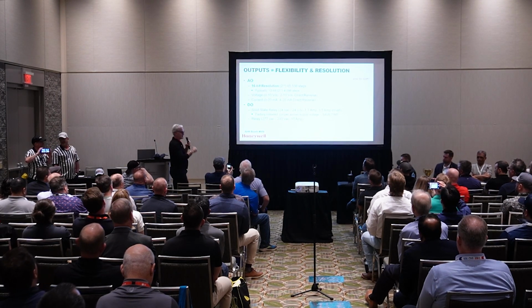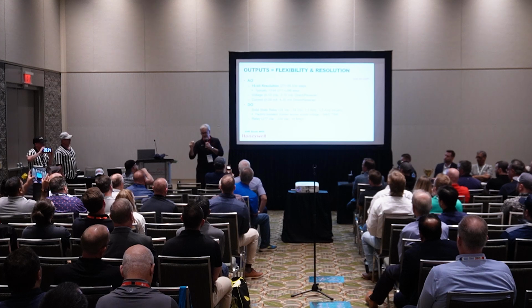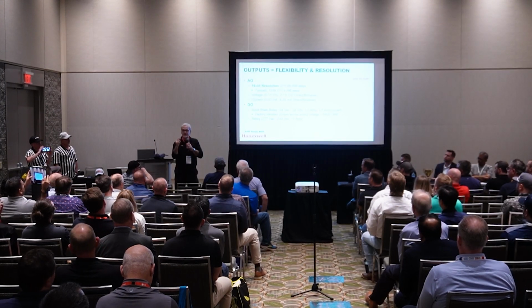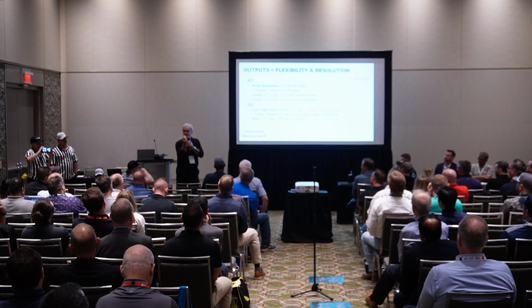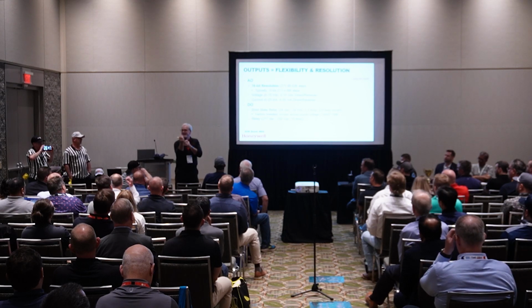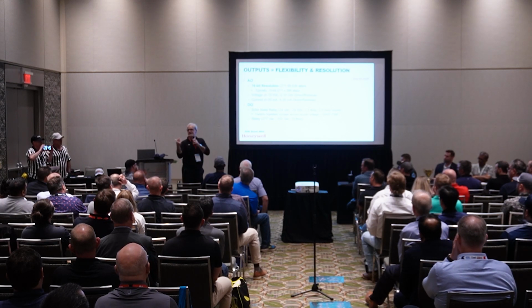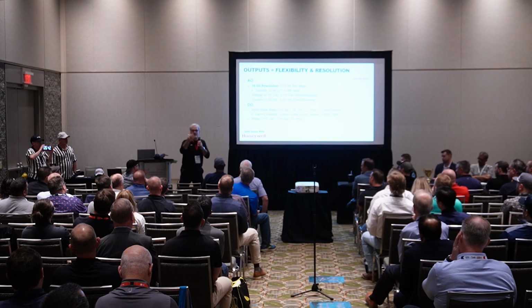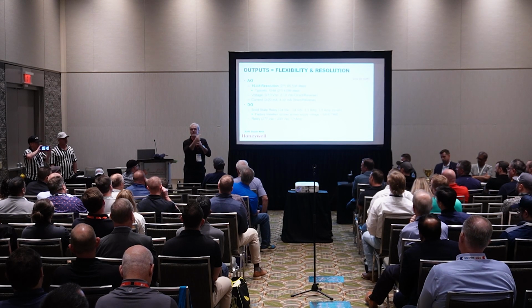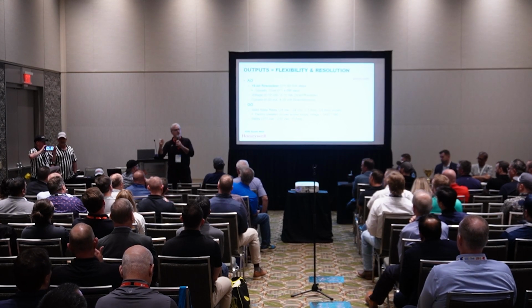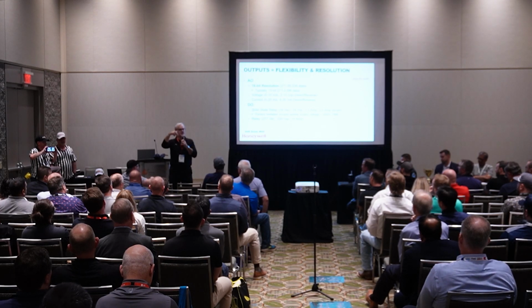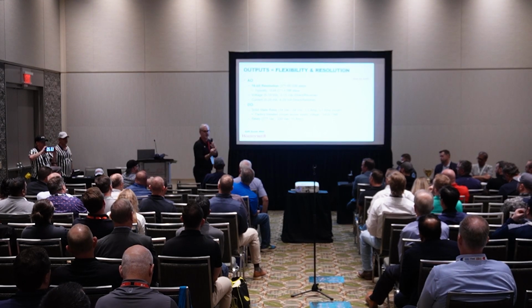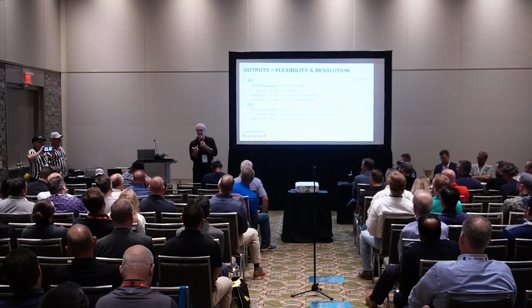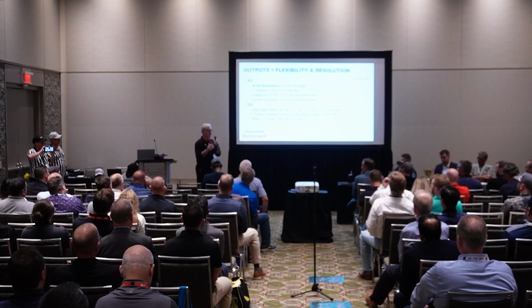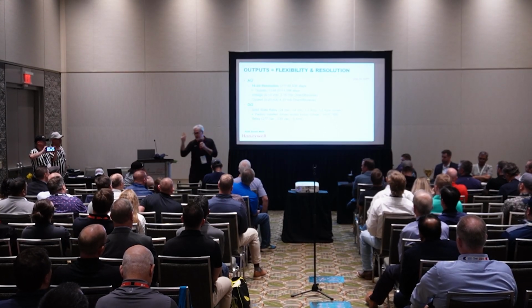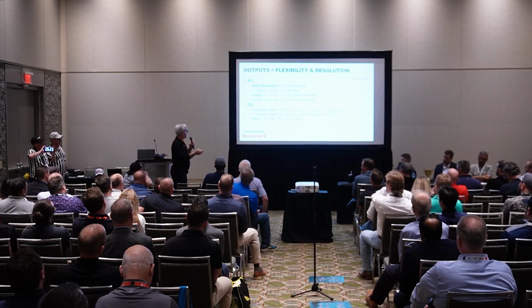Oh, one thing I forgot to mention, we're trying to give you time savings. If I have a milliamp input, I typically have to put a 500 ohm resistor across that input, right? Takes time. Oh gosh, the technician doesn't have any, got to run to Cochran and get some, whatever. Time, money. We've embedded a 500 ohm resistor in all the universal input points. So when you download and commission, if you have a milliamp point, that resistor gets activated automatically. Little time saver. Analog outs, same resolution. Digital outs I already talked about.